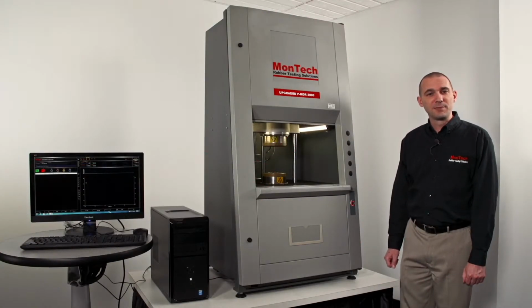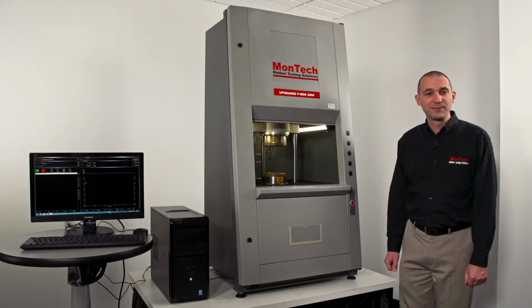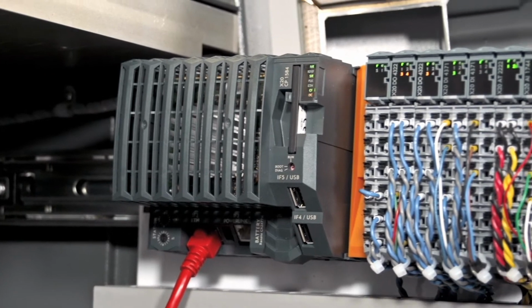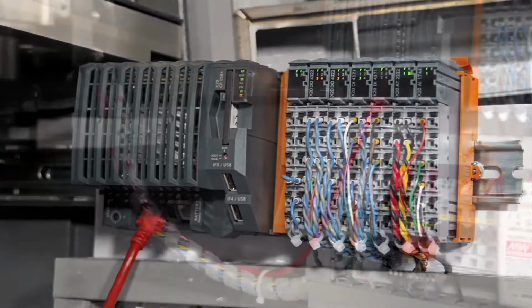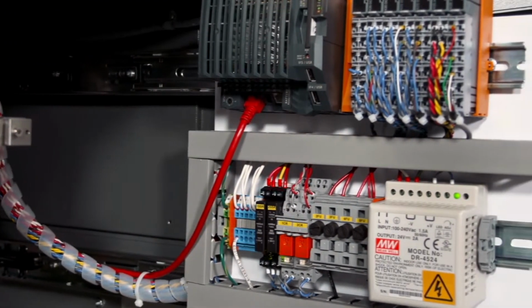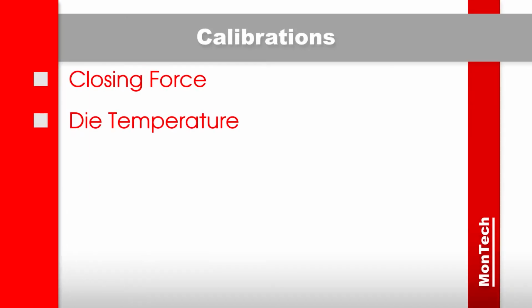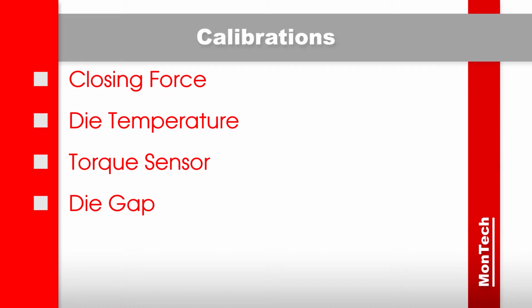The central shaft assembly is checked and new bearings are installed. Old circuit boards and ribbon cables are replaced with a new state-of-the-art MonTech PLC and new wiring.